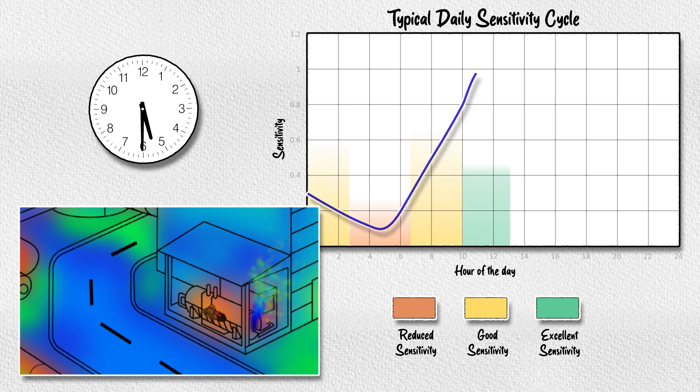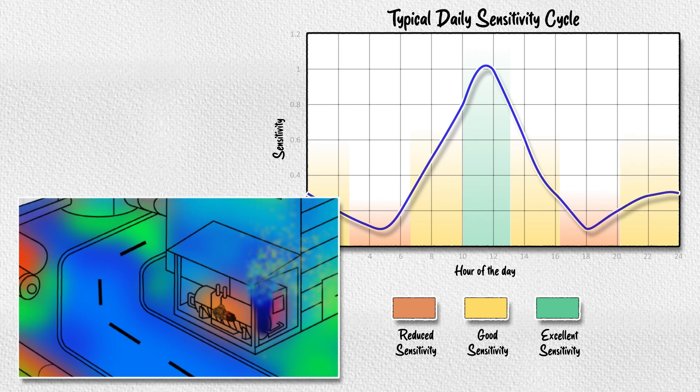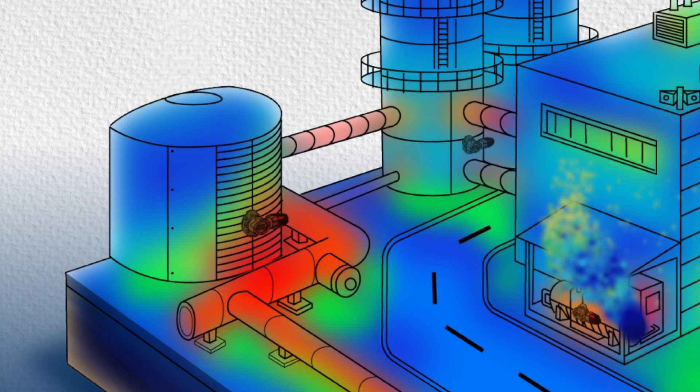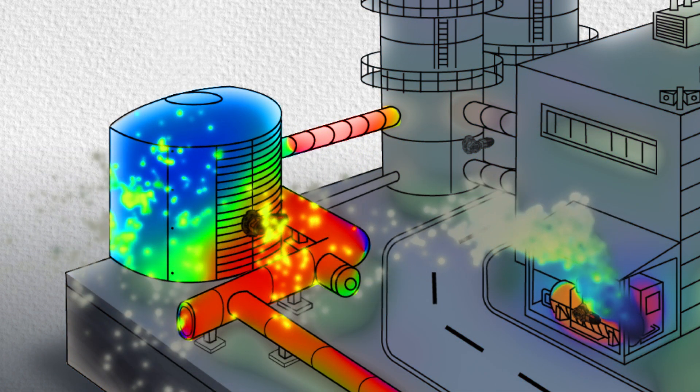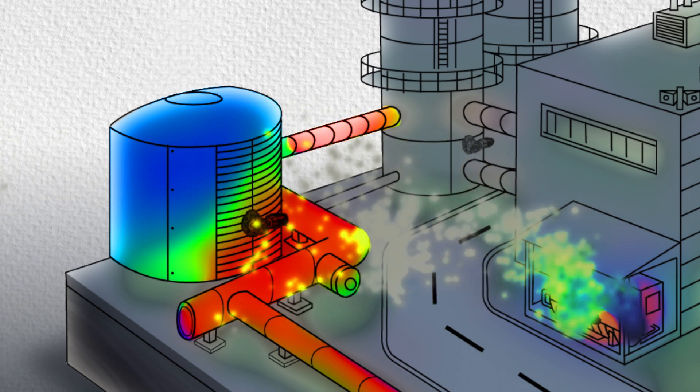Constant leaks will be detected at the high parts of the sensitivity cycle. In locations where the background has an elevated temperature, hot objects like compressor stations, detection sensitivity is constantly high, regardless of ambient conditions.